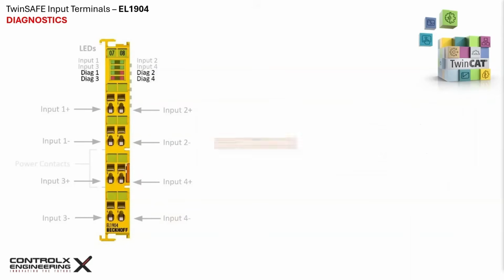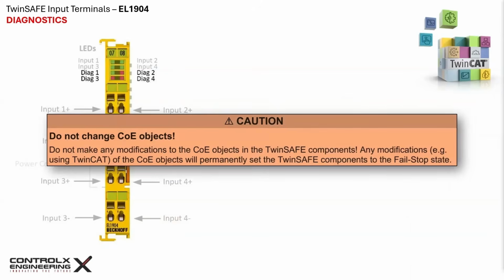I also wanted to point out this warning from the product documentation, which states that modifying any of the CoE parameters of TwinSAFE components in TwinCAT will render that terminal useless. These objects contain safety-critical information such as device identity, safety configuration data, checksums, FSoE communication parameters, and other certified safety logic behavior. As these objects are part of the terminal safety certification, they are not meant to be modified by the user. Any modification is seen by the TwinSAFE device as tampering and immediately locks itself into a permanent fail-stop state. In short, all device configuration must be done through the TwinSAFE workflow and not by editing CoE objects directly.